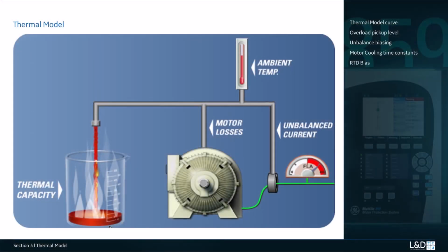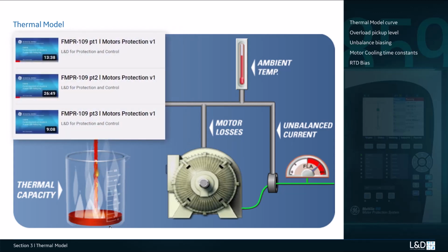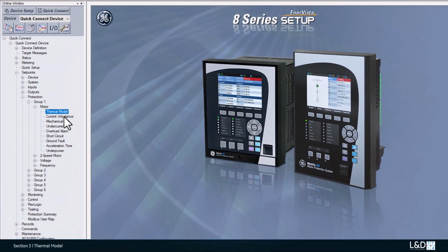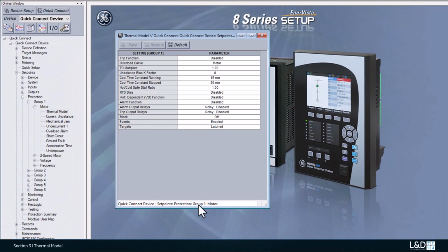The 859 thermal model is a main protection function. It consists of the 5 key elements: the thermal model curve, overload pickup level, unbalance biasing, motor cooling time constant, and RTD bias. For the detailed theory about the thermal model, please refer to the FMPR training modules 109 motor protections. The thermal model is saved under motor and of the group 1.